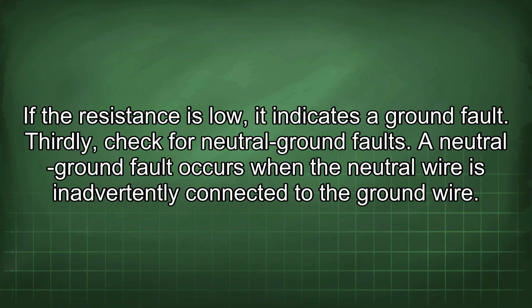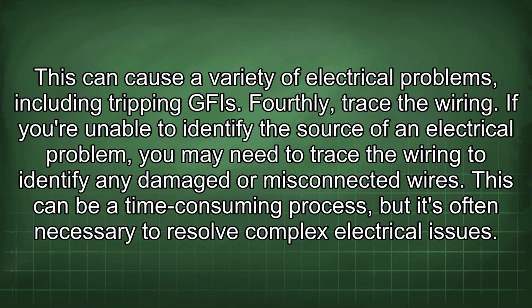Thirdly, check for neutral ground faults. A neutral ground fault occurs when the neutral wire is inadvertently connected to the ground wire. This can cause a variety of electrical problems, including tripping GFI. Fourthly, trace the wiring. If you are unable to identify the source of an electrical problem, you may need to trace the wiring to identify any damaged or misconnected wires. This can be a time-consuming process, but it's often necessary to resolve complex electrical issues.